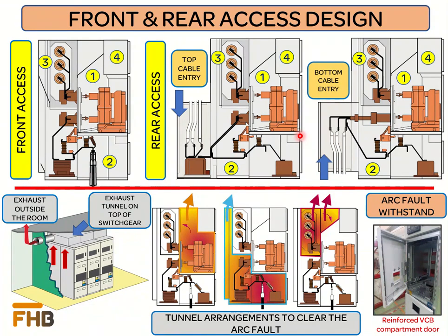Either it is a front-access design or a rear-access design, the LSC2B requirement of IEC 62271-200 will remain applicable, and four clear compartments, the circuit breaker compartment, the cable compartment, the busbar compartment and the LV box will be required.